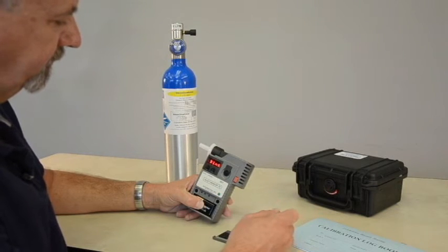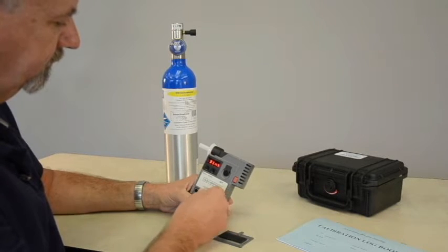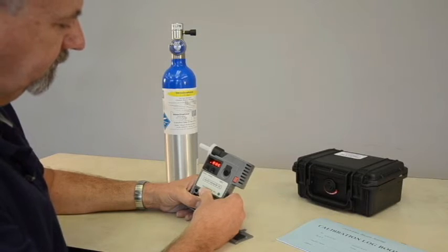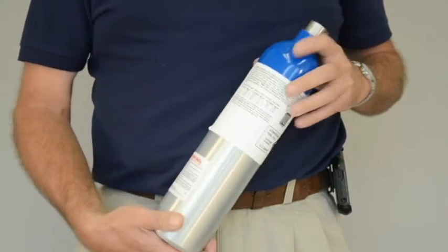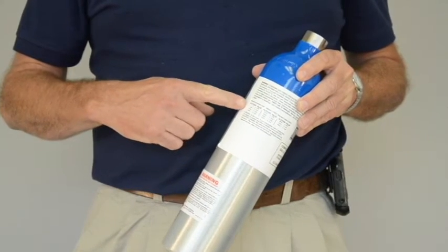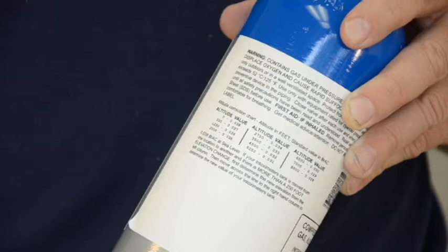Before performing a calibration, you must first locate the expected value of your gas standard. The expected or target value of your gas standard can be derived by referencing the altitude chart on the back of your tank.